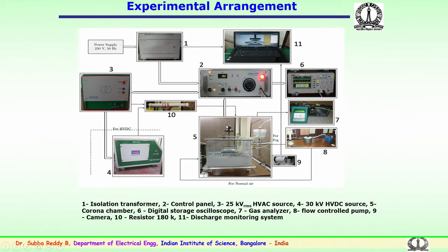The sample is kept here, the high voltage is connected and continuously monitored over a period of tens of hours or 100 hours, and the performance of the samples is checked for AC and DC. We have a facility for this chamber where we can inject natural air, or a fog, or an acidic fog, and the effect on the samples can be studied. So, this is a specially made chamber, and the corona activity is monitored in the monitoring system, and the leakage current is also measured using a digital storage oscilloscope.